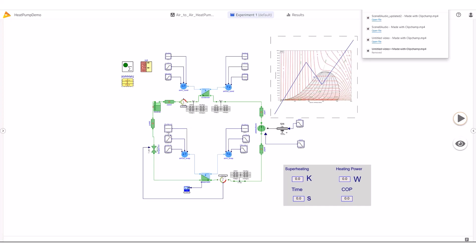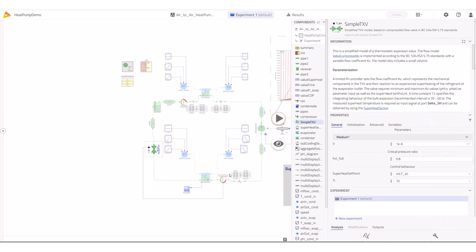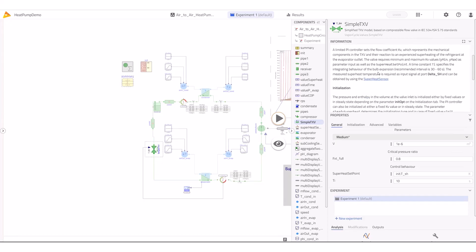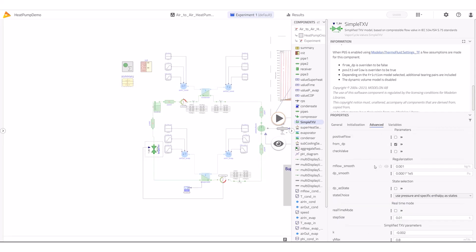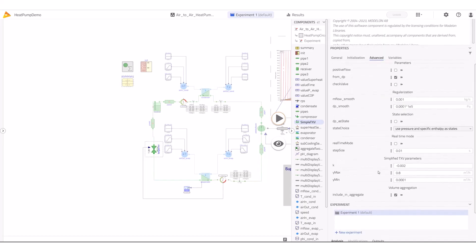Let's now explore the effect of superheating on the system. Superheat is controlled by the expansion valve, which regulates the mass flow to reach the desired superheat level at the evaporator outlet. Exploring this expansion valve, I can see that among the different parameters we have the superheat setpoint. If we go to the Advanced tab, I can also see the parameters for the internal controller. This controller, together with the valve characteristics, models the physics of the valve and, as mentioned, regulates the mass flow.